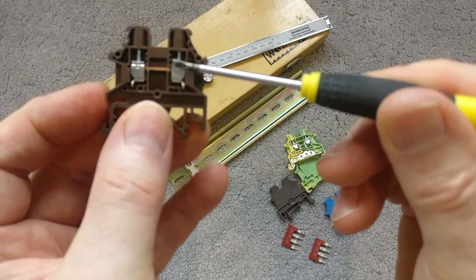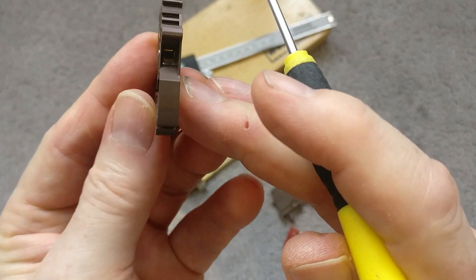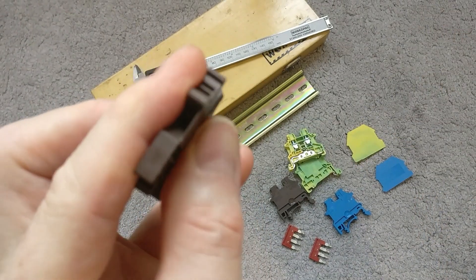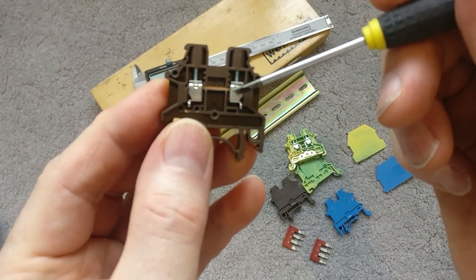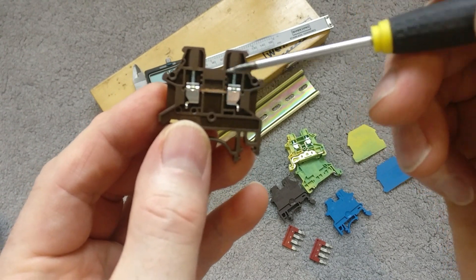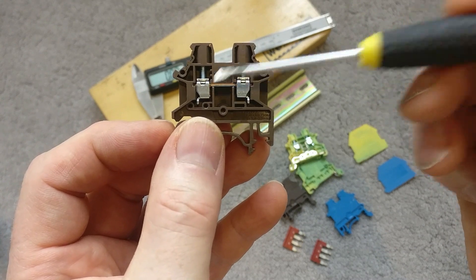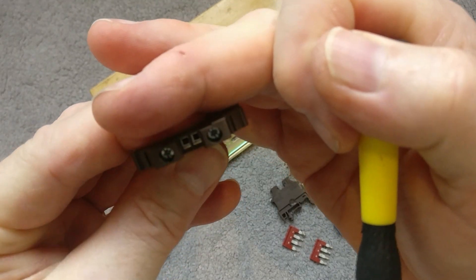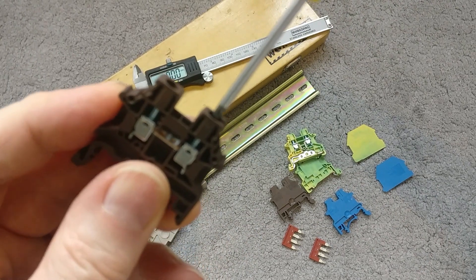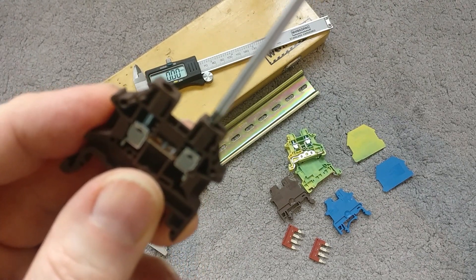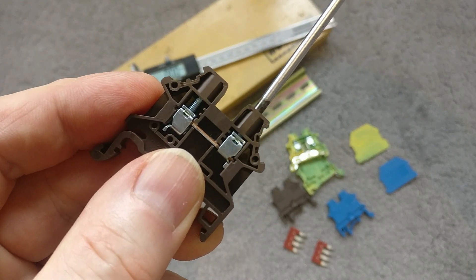Looking inside, you can see there's a clamp on either side. There's a little hole, the cable goes into this hole, and then this clamp clamps it to this common copper bar. So once you've got a cable in here, the current can flow through onto this side. If you can see in the top there, there's a Phillips screw at the bottom. If you put a screw in and turn that, you can see that clamp is raising up, and then that would pull the cable onto the copper bar and give you a really good mechanical connection.